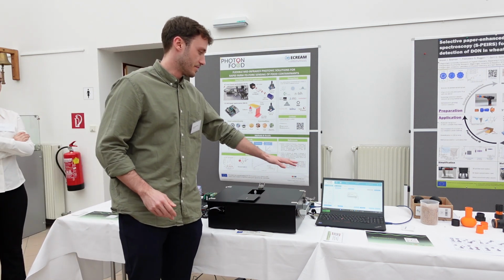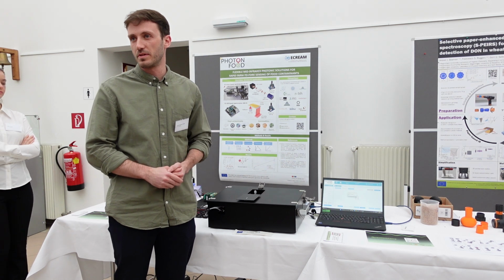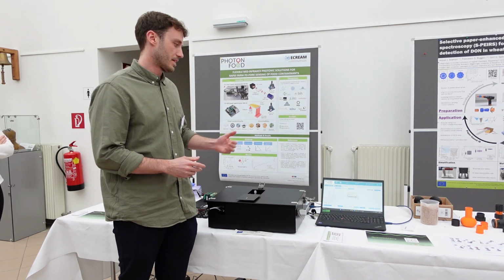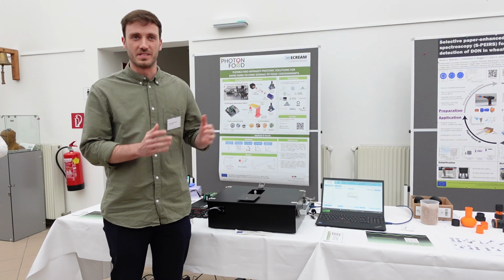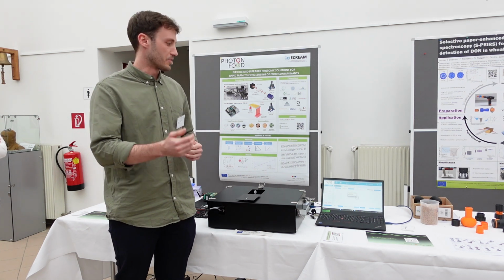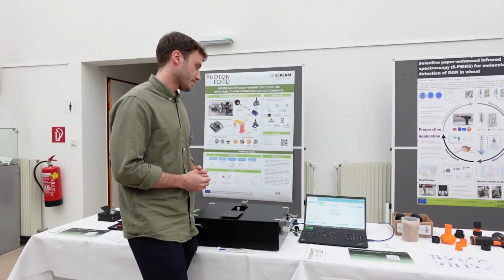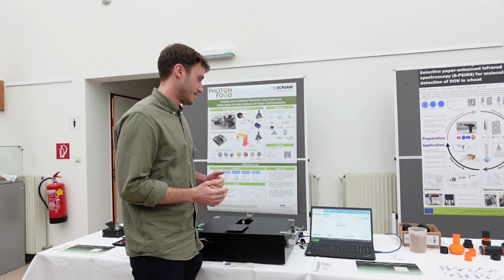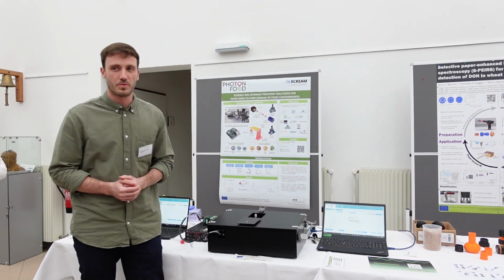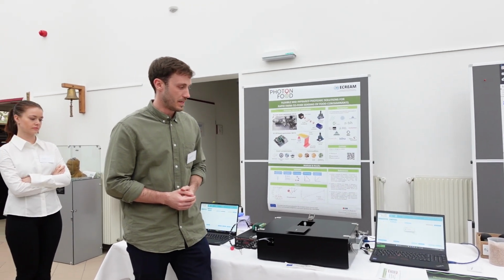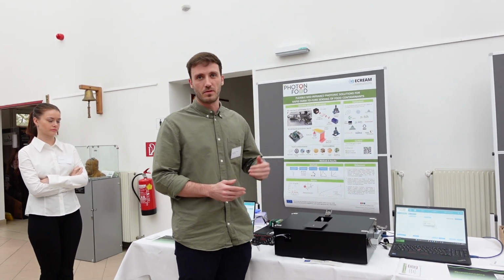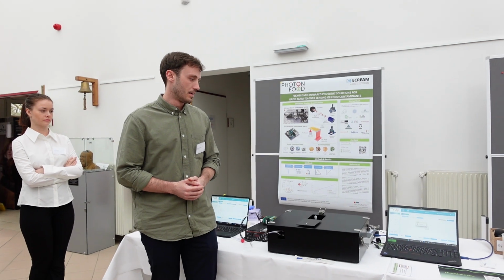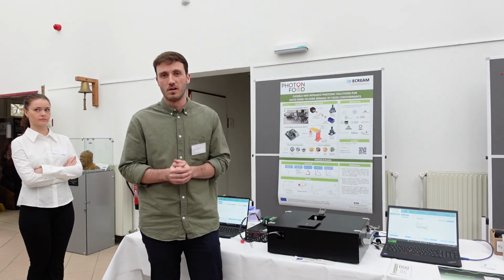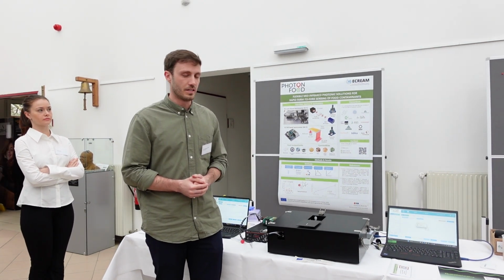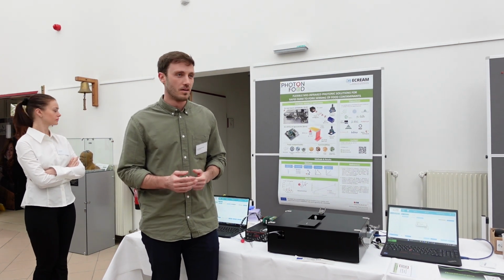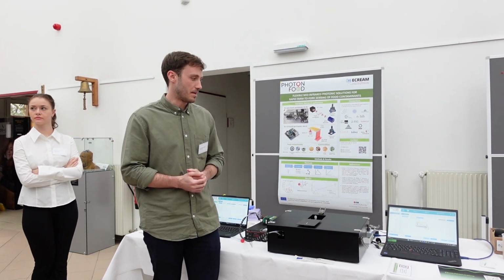After that, it has different settings, like uploading models that are already there. So it can give a direct response if the sample is contaminated with DON or not, according to the data calibrated before. Now it will just be waiting again for the process, and then you will have the data log with all the measurements done on that day. So you can also upload the spectra there and compare them across the different samples.